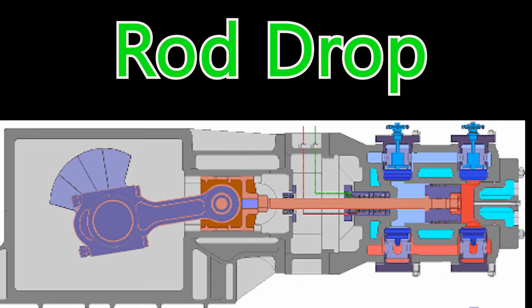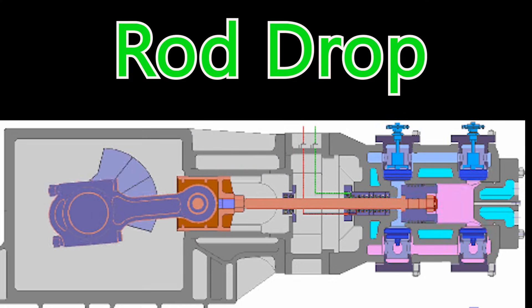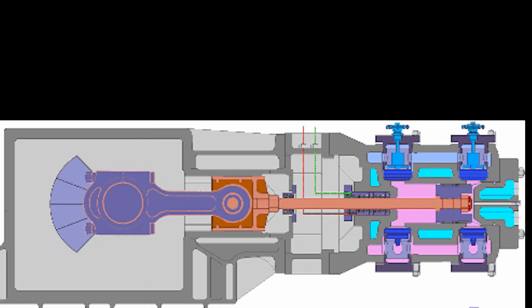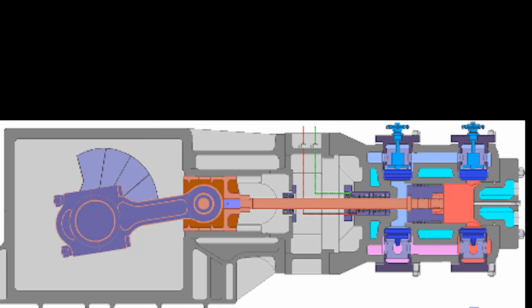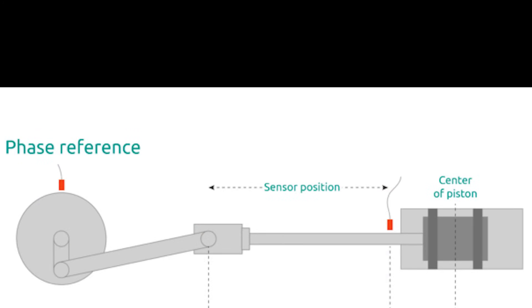Proximity probes can also be used on reciprocating compressors to track the amount of band wear that occurs as a piston slides in and out of the cylinder. These types of devices are typically referred to as rod drop sensors. In this application, a proximity probe is installed perpendicular to the shaft, either above or below.